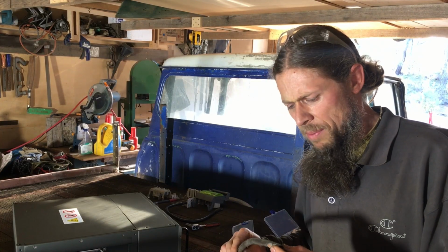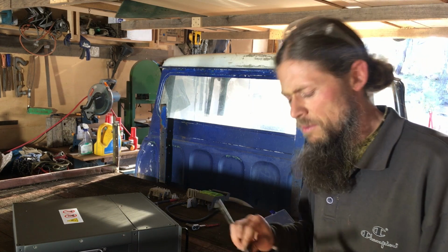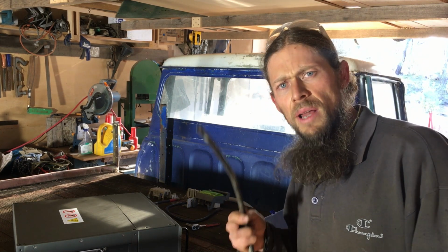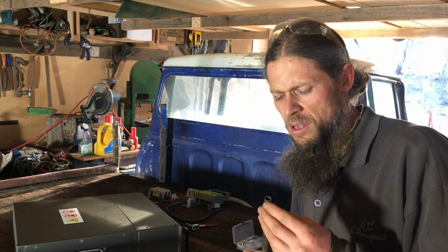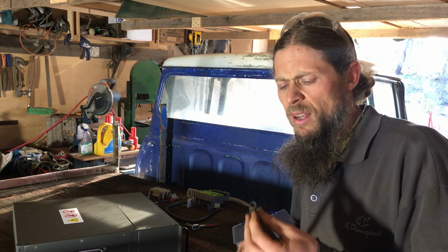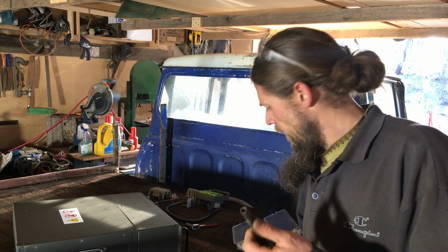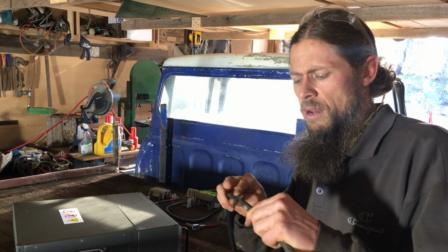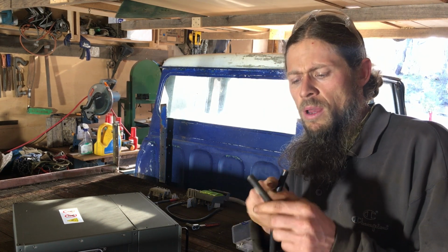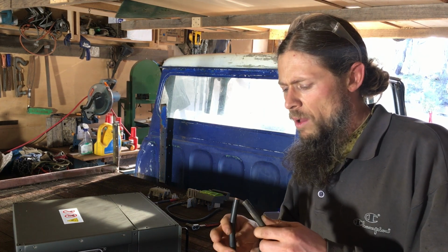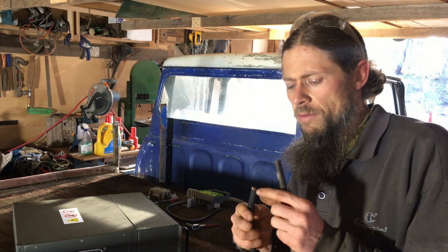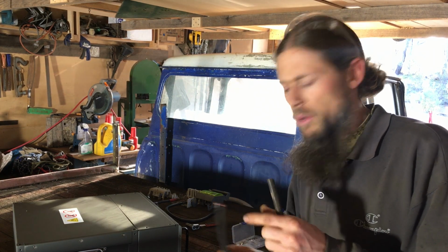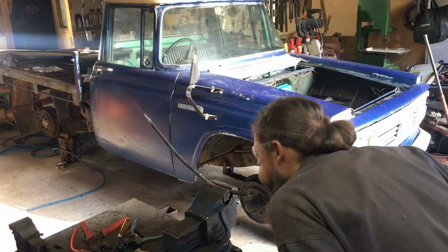I've got some copper pipe here, but it's secondhand and old, so we're gonna scrub it up to make sure it's got fresh copper on the outside and inside, then crimp it onto the end of our 35 square mil cable with a flattening on the end, drill a hole, and solder it on so no verdigris or crap can get between the two. Let's make some lugs.